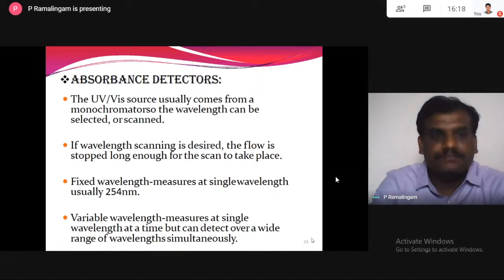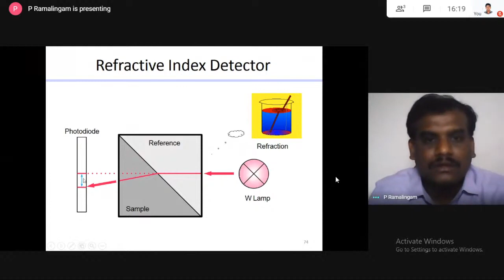So this is called a refractive index detector, and you can see the lamp, the light is passing through the sample. One is a reference, another is the sample. There is a refraction, and this is your reference detection. This is your sample detection. This difference is taken as a signal. But this refractive index detector is universal, but it has a poor detection limit. The detection is very poor. It is one of the major disadvantages of the refractive index detector.